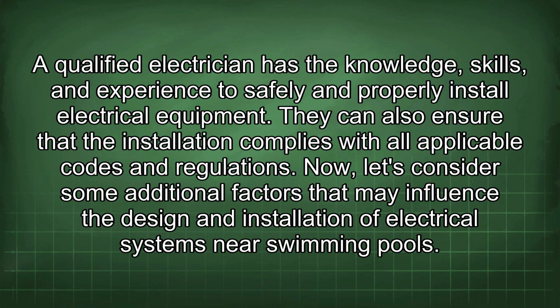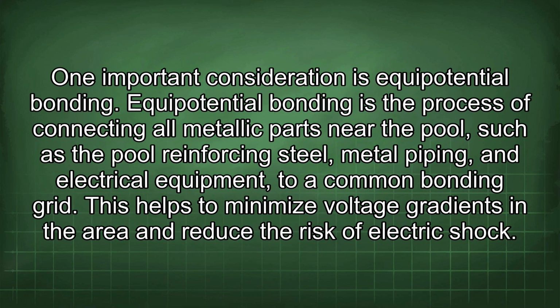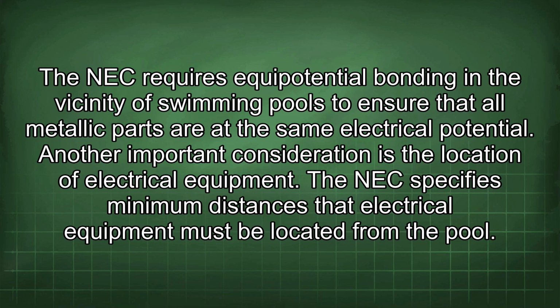Now, let's consider some additional factors that may influence the design and installation of electrical systems near swimming pools. One important consideration is equipotential bonding. Equipotential bonding is the process of connecting all metallic parts near the pool, such as the pool reinforcing steel, metal piping, and electrical equipment, to a common bonding grid. This helps to minimize voltage gradients in the area and reduce the risk of electric shock. The NEC requires equipotential bonding in the vicinity of swimming pools to ensure that all metallic parts are at the same electrical potential.